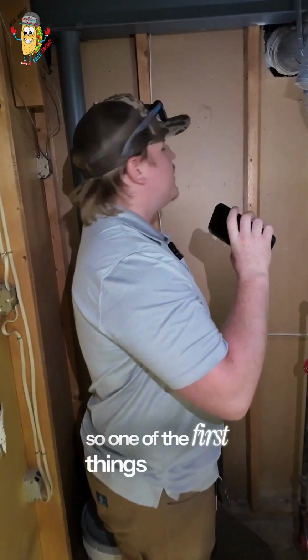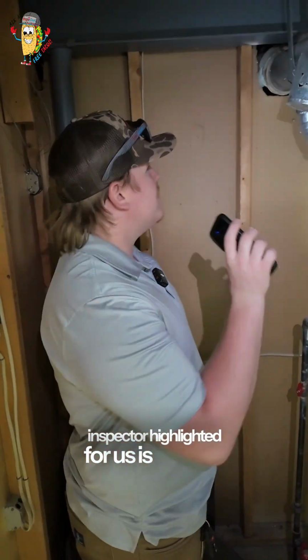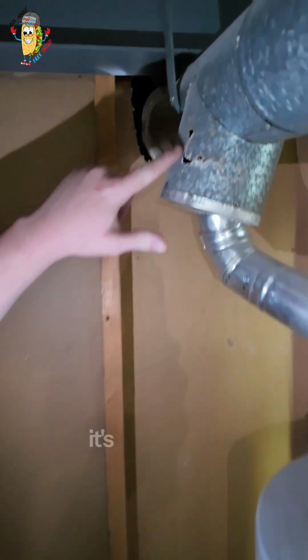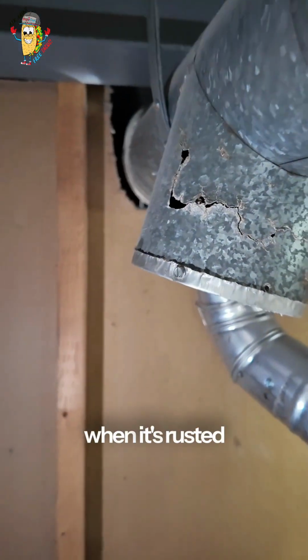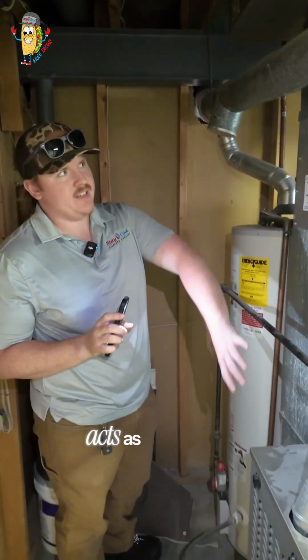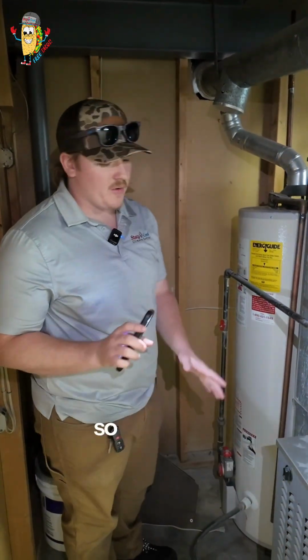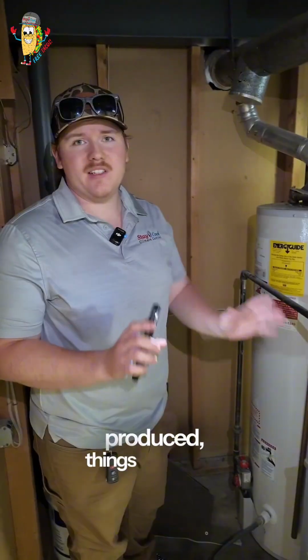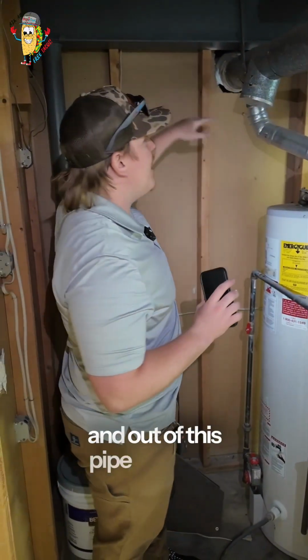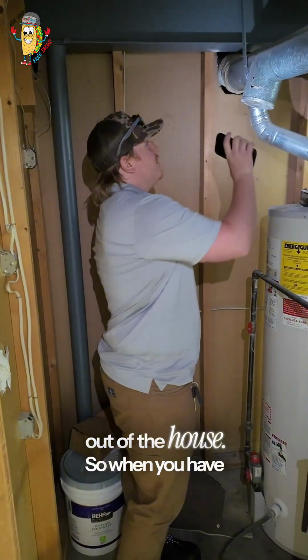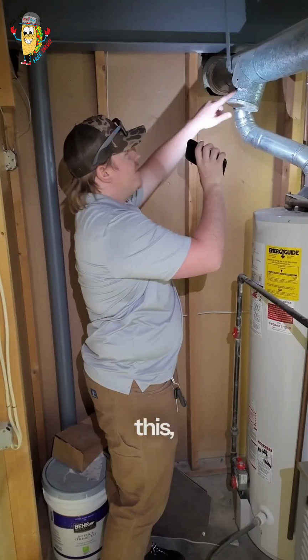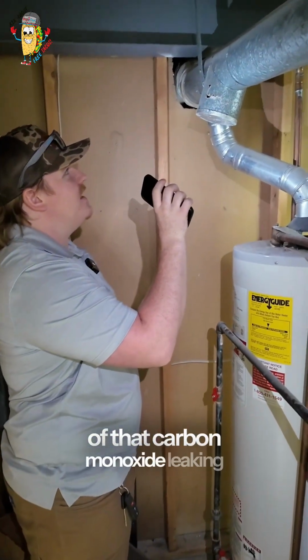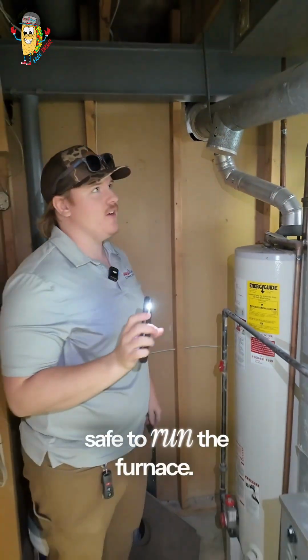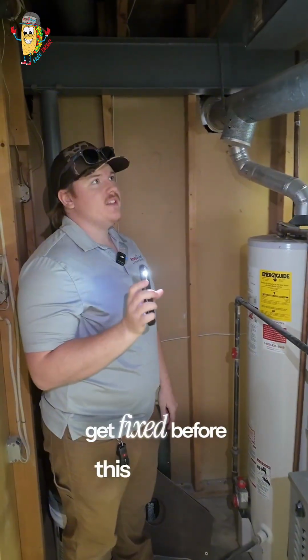Okay, so one of the first things that the inspector highlighted for us is the flue right here. As you can see, it's got a big old crack in it from when it's rusted through. This flue pipe essentially acts as an exhaust for the furnace. So all the flue gases that are produced, things like carbon monoxide, get vented up and out of this pipe and then out of the house. So when you have structural compromisation right here like this, it creates a risk of that carbon monoxide leaking into the house, making it not safe to run the furnace. So definitely going to need to get fixed before this house is ready to sell.